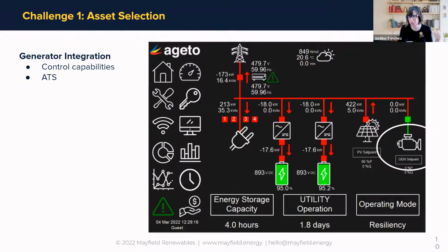Because one of the things we're always worried about is PV trying to push into the generator, and that's where curtailment comes in. Okay. We have a few systems that are just solar diesel systems with no energy storage. In that case, we have to keep the generator running to be the grid forming asset in the system, but we curtail the solar on a second by second basis to provide a minimum loading set point, typically 20% or 40% loading on the generator. That allows it to operate using less fuel, but also efficiently, and not cause any performance issues of underloading or reverse powering the generator.